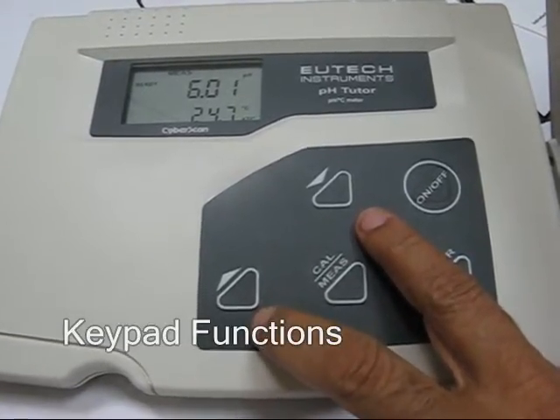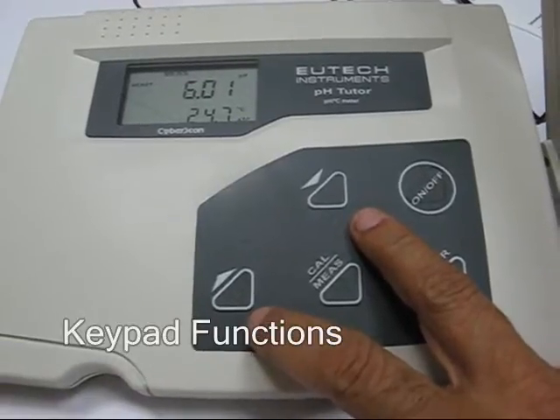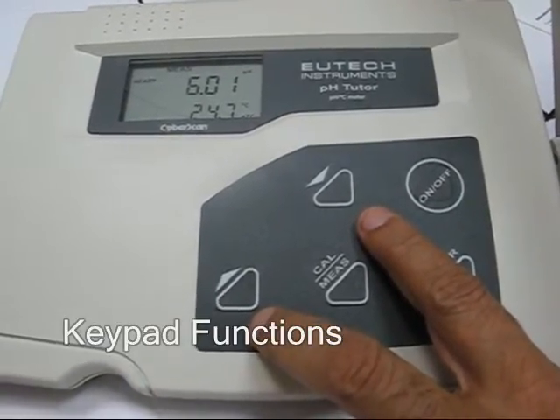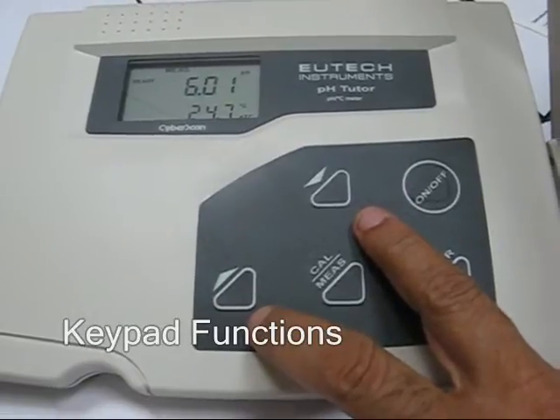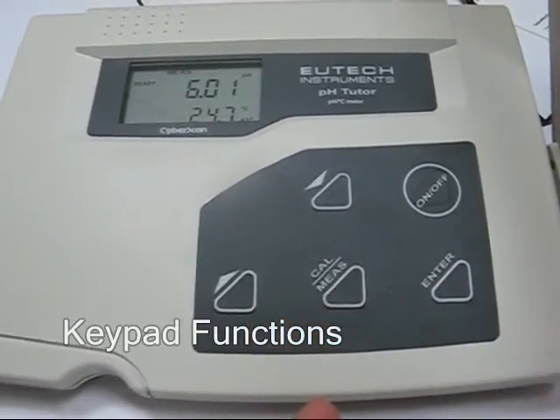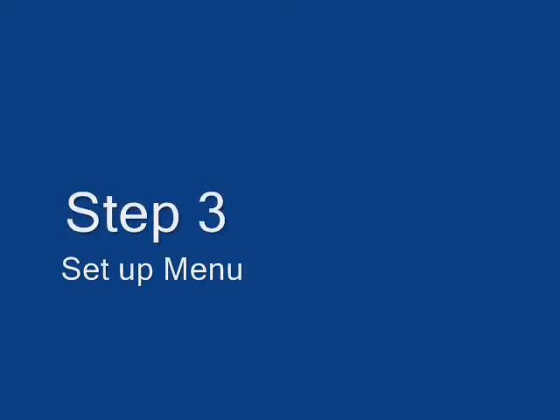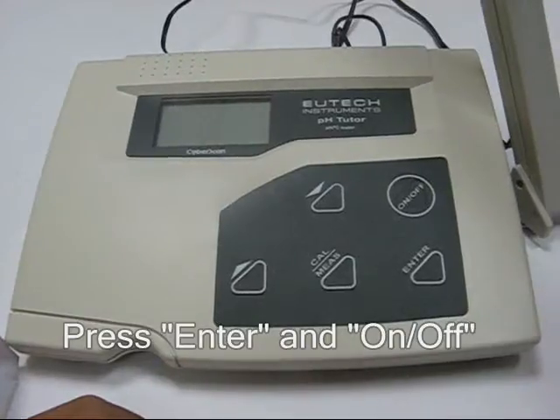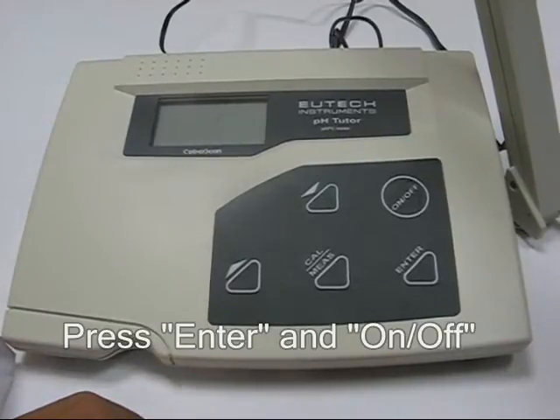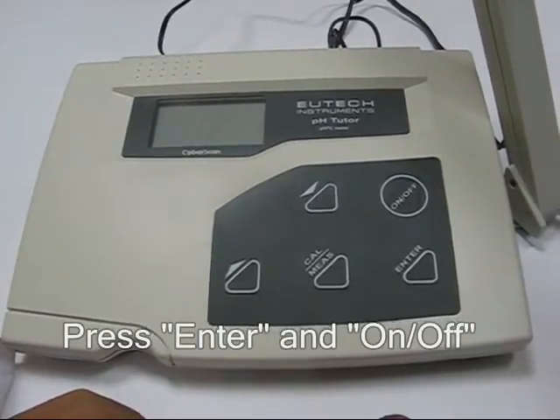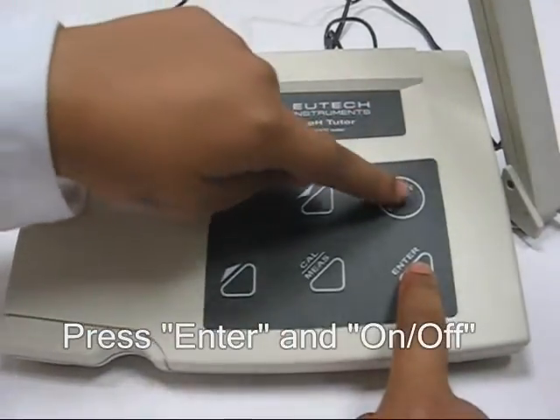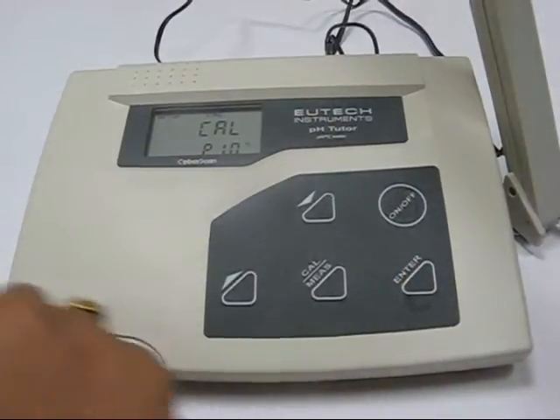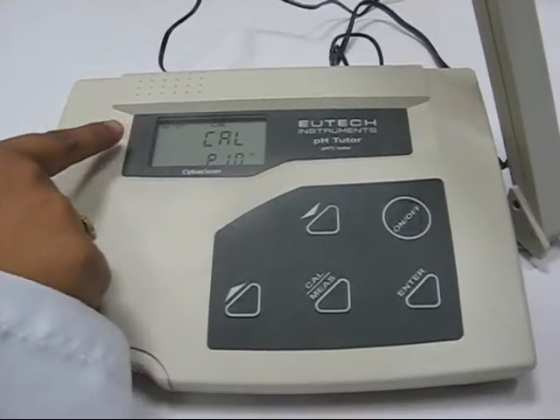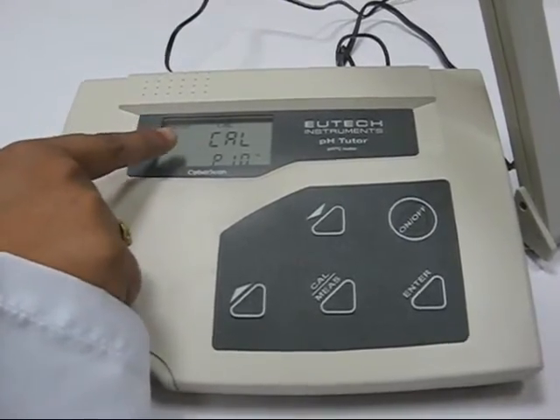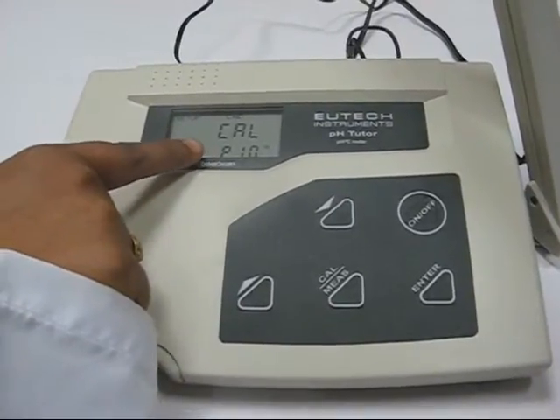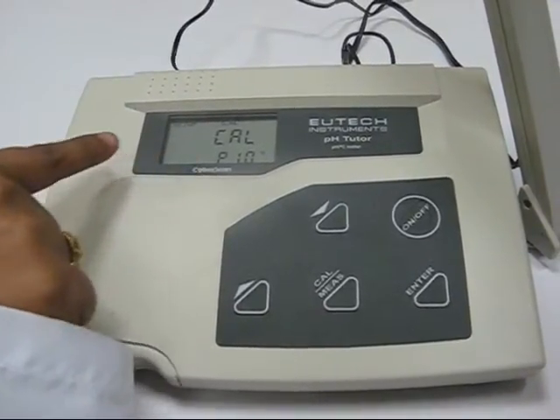These two keys will help you toggle between the various menu selections, and if you are inside a menu, it will help you change a particular setting, and then you press the enter key to confirm the selection. We will now see how to go through the setup menu. For this, you need to power the unit on with the enter key pressed. Let's do it. You now see the upper display says cal and then the lower display says P1.0. This means that you are in the program menu 1.0.